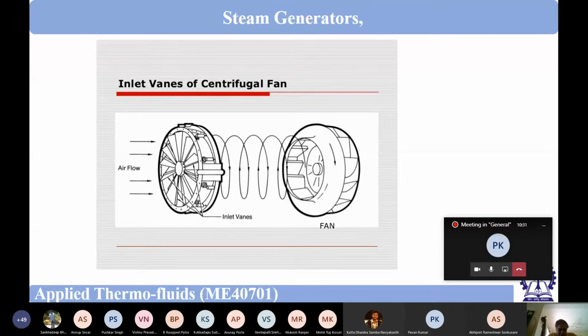I can give an example, though exactly they are not similar. If you have looked into a mechanical camera, the aperture control, how the apertures are controlled, there are a number of circular segments, and they overlap on each other, and ultimately the aperture becomes larger or smaller. In a similar way, the inlet vane also controls the inlet area. And obviously, there will be resistance, but the flow will remain more or less uniform. So this is another aspect.